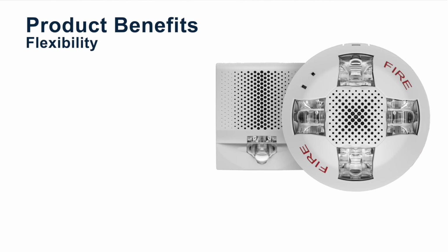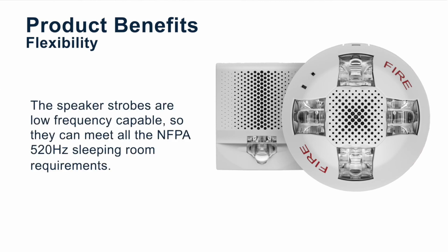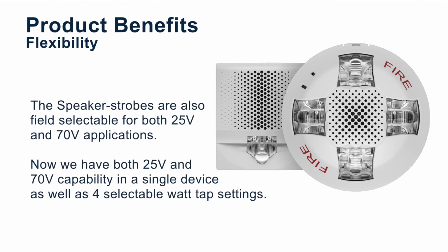The Genesis LED speaker strobes also offer flexibility. The speaker strobes are low frequency capable, so they can meet all the NFPA 520 Hz sleeping room requirements. This is especially important as NFPA and local codes are expanding the definition of what qualifies as a sleeping room. The speaker strobes are also field selectable for both 25 volt and 70 volt applications. So now we have both 25 volt and 70 volt capability in a single device, as well as 4 selectable watt tap settings. And we're not done.